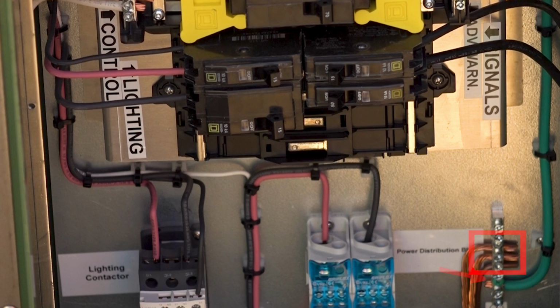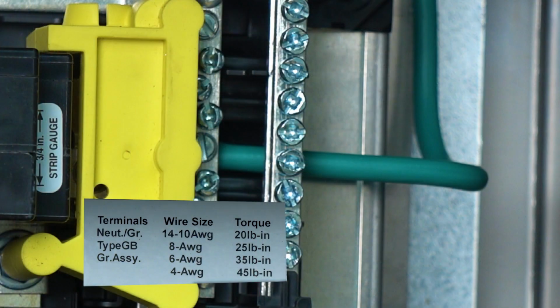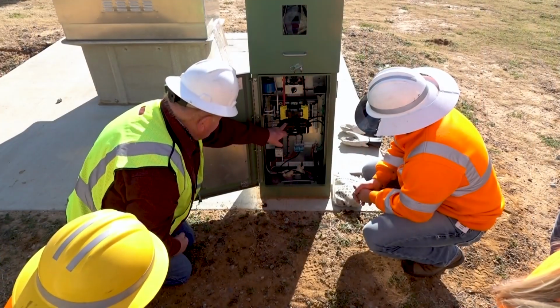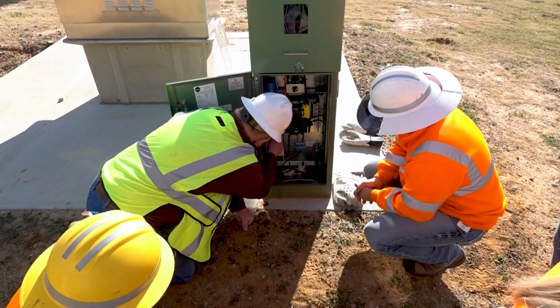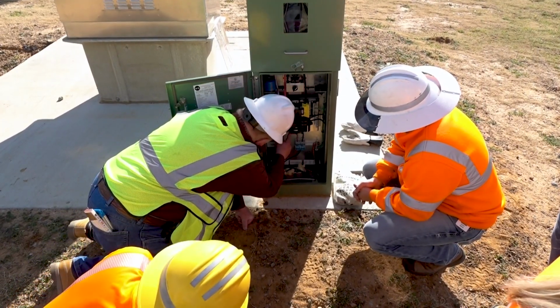The NEC requires a green-headed main bonding screw to bond the bus bar to the enclosure. The bus bar must have a label near it listing the correct torque value for the screws that secure each conductor to the bus bar. The torque value should be verified by the installing contractor. The inspector should examine each conductor to confirm it is secure and undamaged.